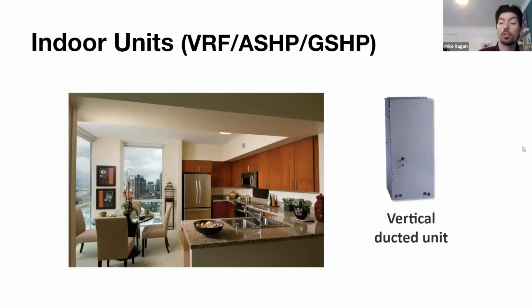And certainly the vertical, or rather multi-positional style ducted unit. This is very common in apartments or condo complexes, especially in retrofit applications where there is an existing vertical stack style fan coil, and we want to minimize the amount of rework we're doing to the space. This will fit directly into those types of box outs. It will fit directly into the closet space, and they have minimal clearance to the side, so full service access directly to the front. And these units are also available with electric heat kits for any particular circumstance where you want to have emergency backup heating built into your system for any heating pickups you may need to achieve.